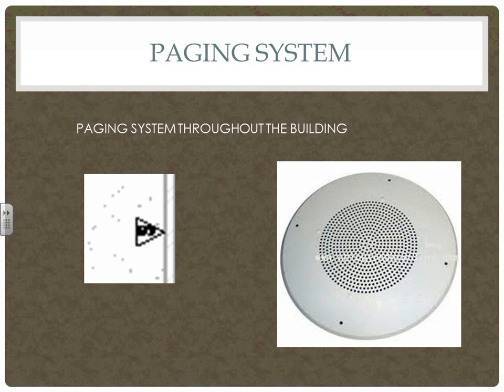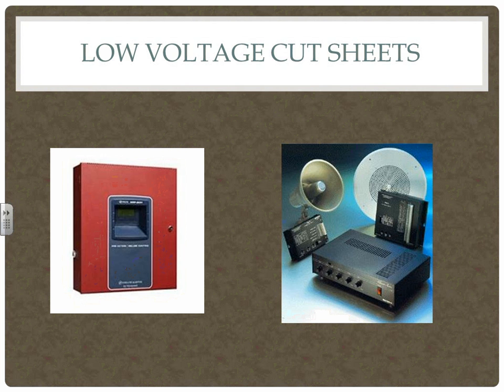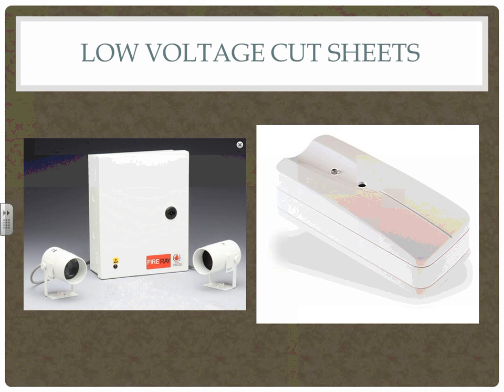There was a paging system throughout, and we had a speaker come in and explain a lot to us, including the different parameters and decibel levels you need. On the manufacturing floor it would be a lot louder, so you have to have a much better, more intrinsic system. That's what these were, kind of like horns on the walls, and then in quieter spaces, just ceiling speakers. Here are some cutout pictures of what we had. This is the pre-action fire alarm panel. That's the paging system over there. A better look at the horns that would be on the ceiling or wall. This is the beam smoke detector, one sending a signal across to the other, and then a glass break.